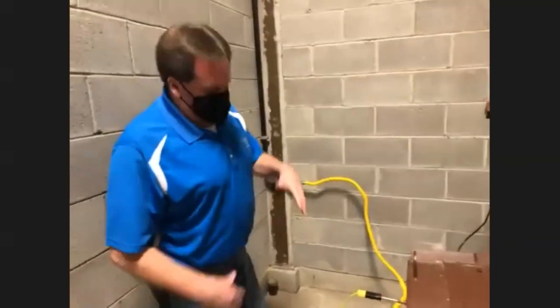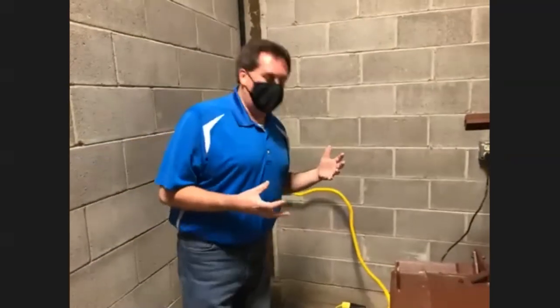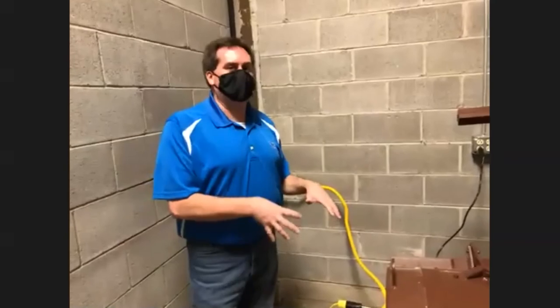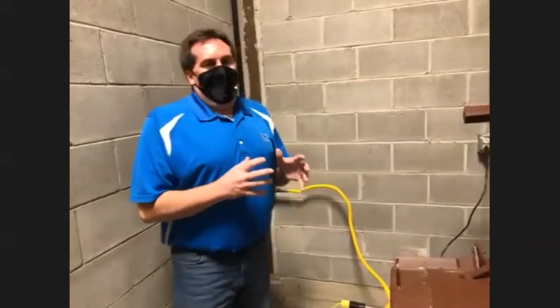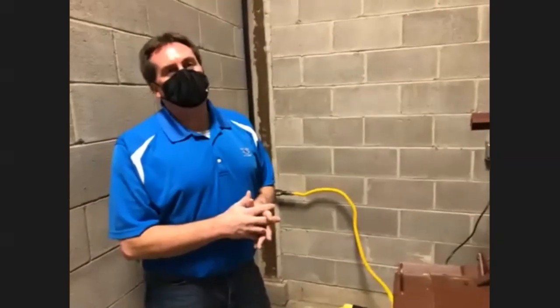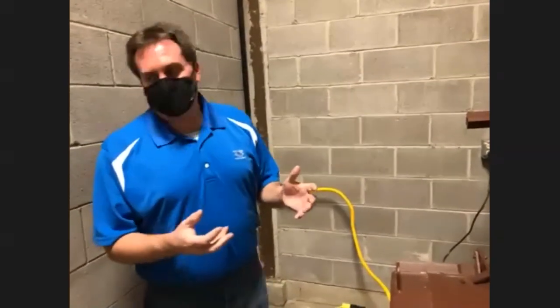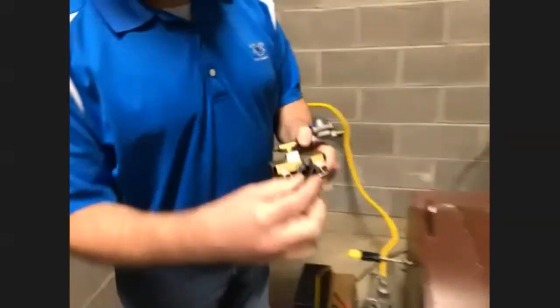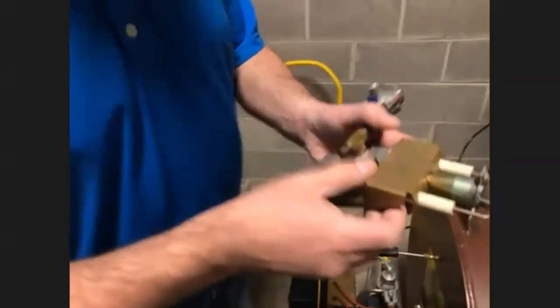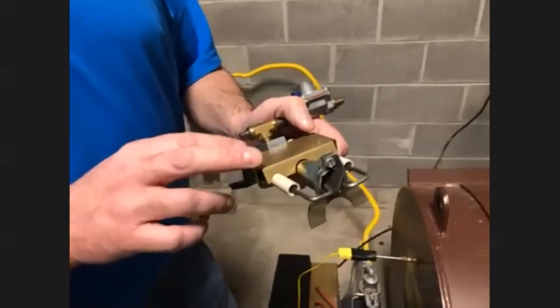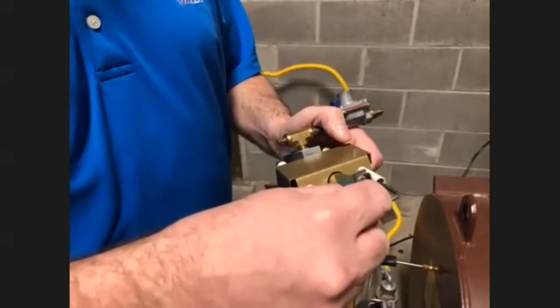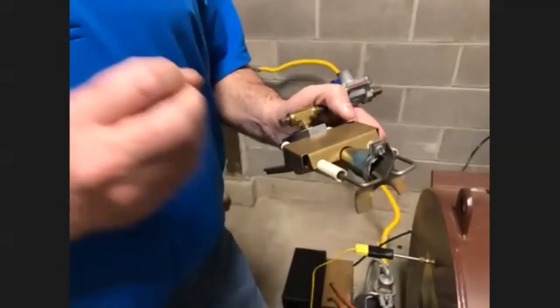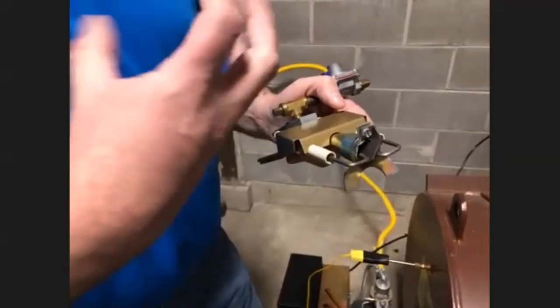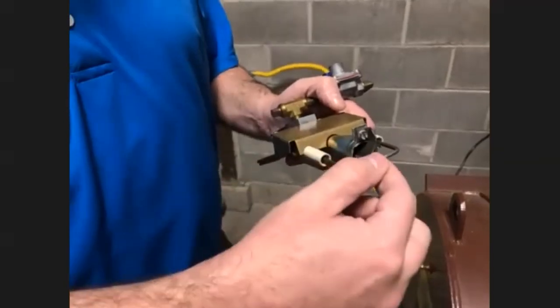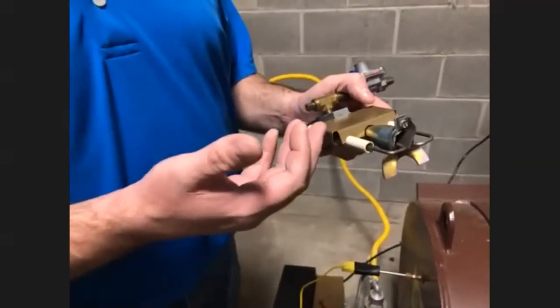As we go through these, you've got everything burning and operating. Now we'll start to go into troubleshooting of these types of systems, the gas burners. With gas burners, the most common maintenance issue you may have is the igniter tips. This is your igniter assembly, and this is where the fuel mixture is coming out. You have your spark electrodes, igniters, and with gas burners, you will get carbon buildup on the tips of these igniters. When you do, it starts to prevent the spark from jumping properly to the ground plate like it needs to for proper ignition.